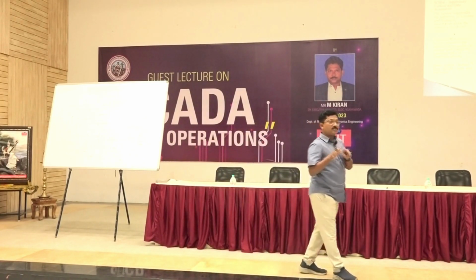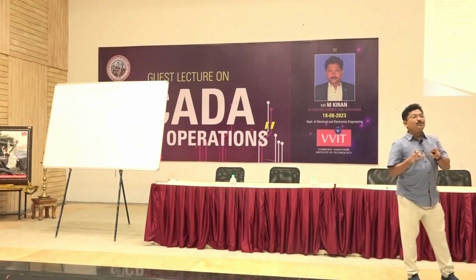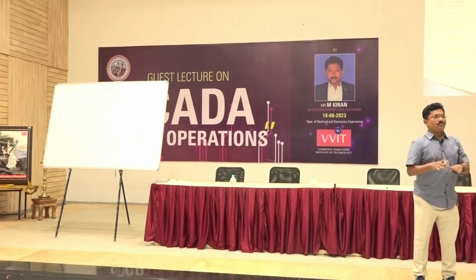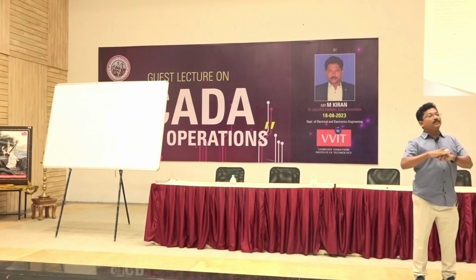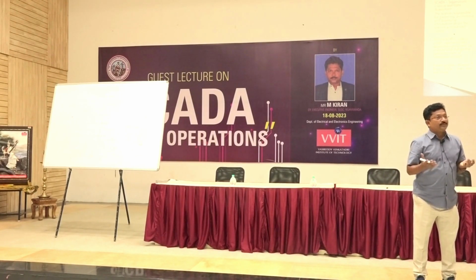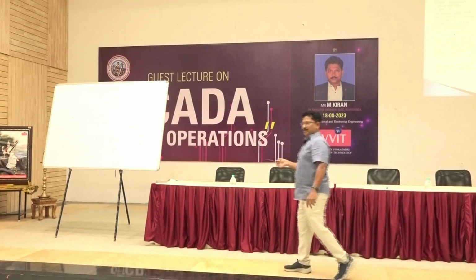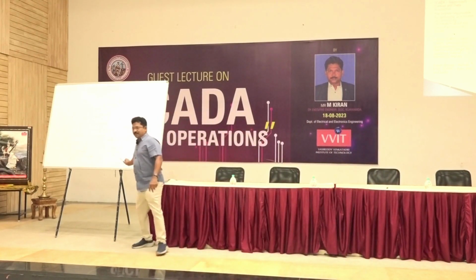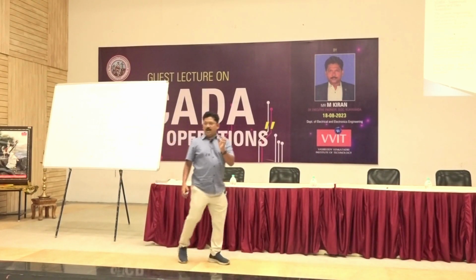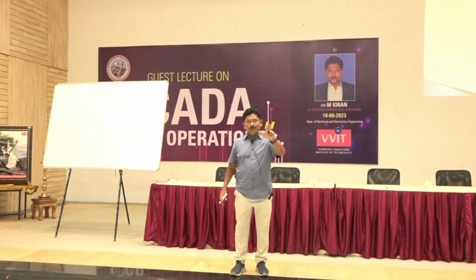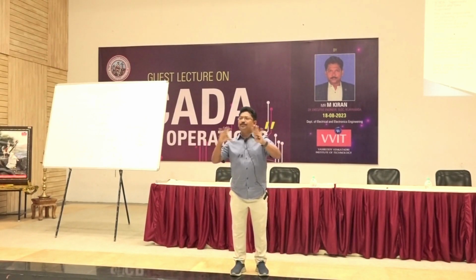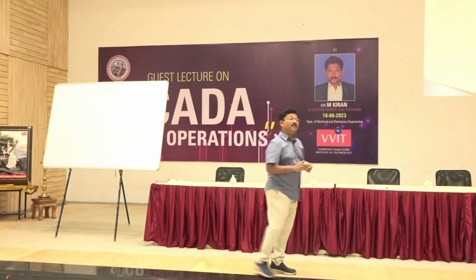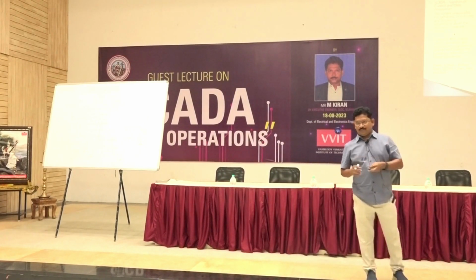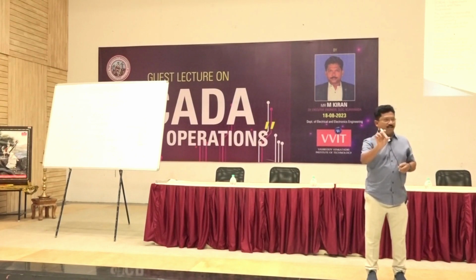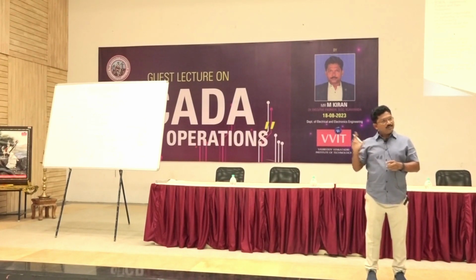Suppose in summer, we used to give power shutdowns for an entire village, for 30 villages at once. How do we do that? Using these signals. So from my system, I can give a DO command which will execute tripping of the breakers in 132 by 33 kV stations. Thereby, 33 kV feeders will go down. I will not rush to the station and trip the breaker myself - using the control center, I am able to do it.